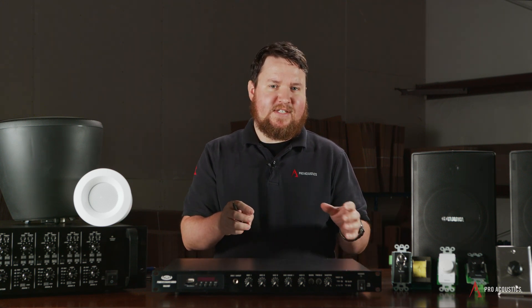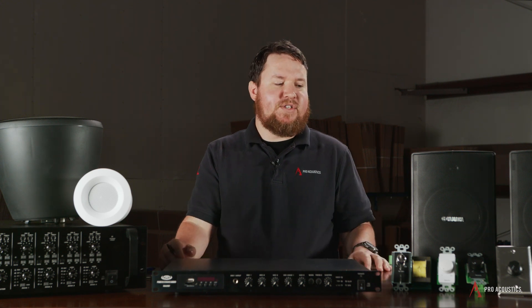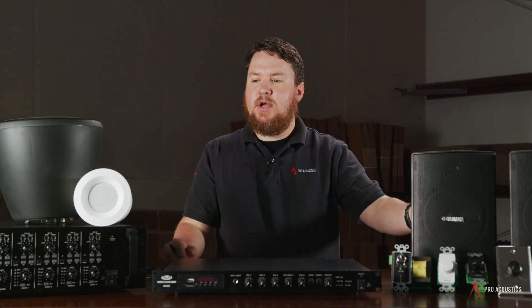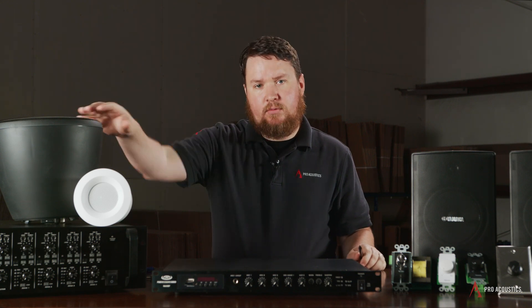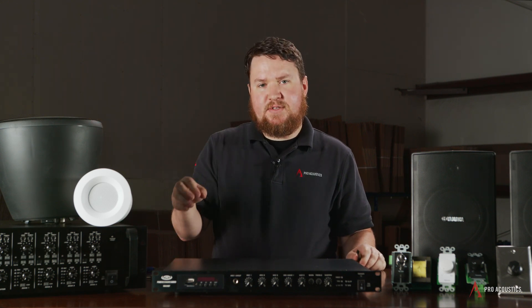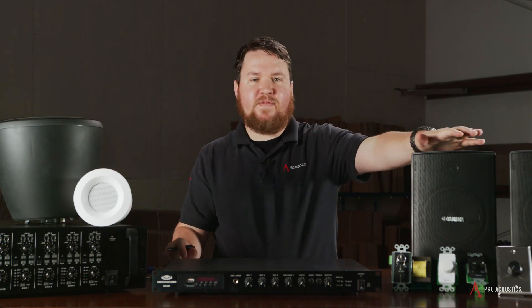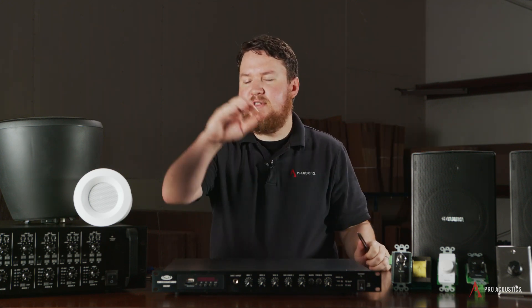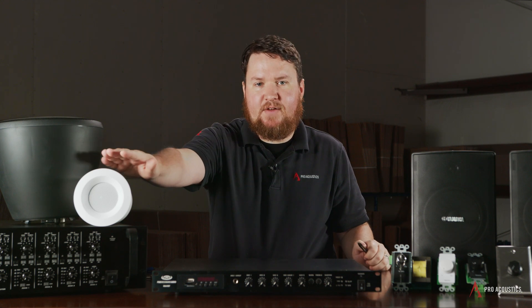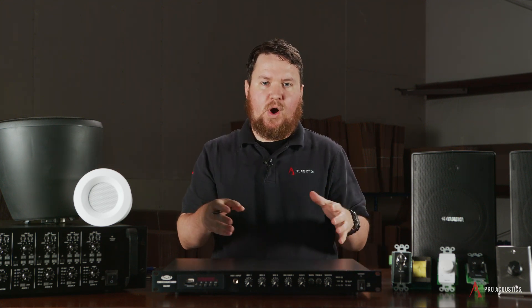We adjust those volumes independently with what's called a tap or wattage tap setting, which is a dial on the back of the speaker, or sometimes it's on the front under a grill, but it allows us to determine how much wattage each speaker is getting. This is a 25 watt speaker with a tap up to 25 watts. This has wattage up to 5 watts, so each individual speaker has its own wattage that can be set in a distributed audio system.